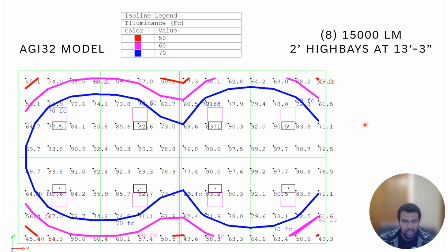And what is a foot candle? What is a measurement that you can relate this to? Typically in your home, 10 foot candles is about what your living room's going to be when you have a couple lamps turned on and maybe an overhead fan light. In a shop space, you're going to have more light because you're doing high detailed work. I am of the opinion that the more light, the better, because you can't add more lumens, but you can put a dimmer on it and make less lumens.